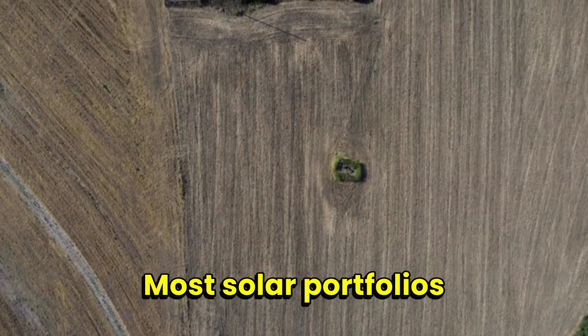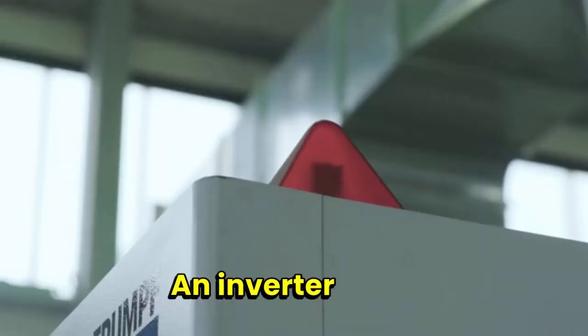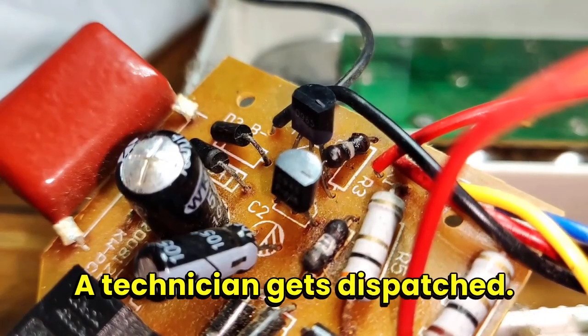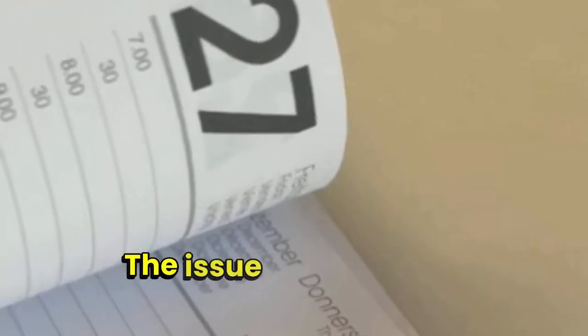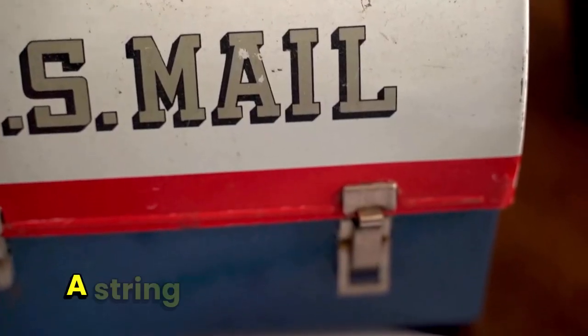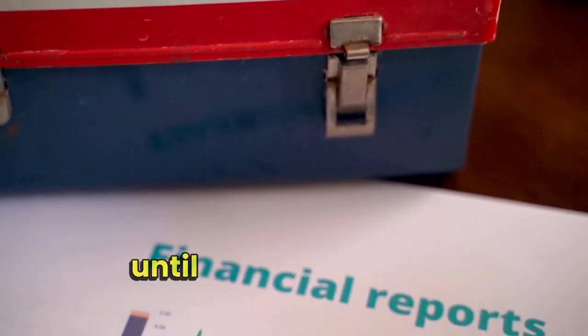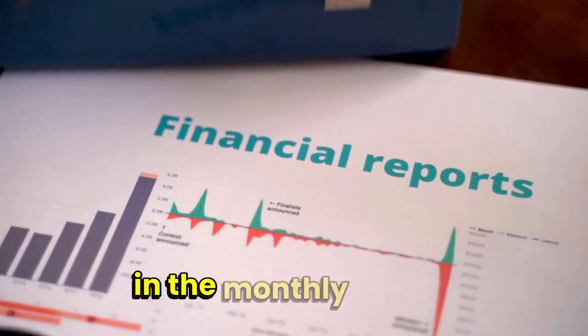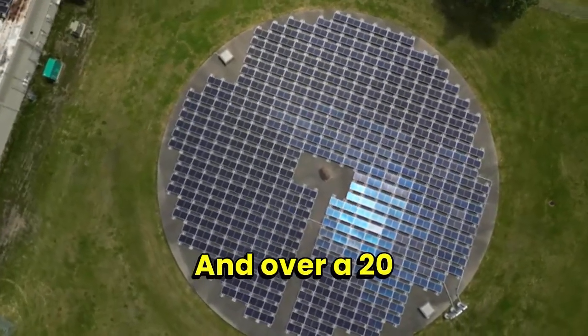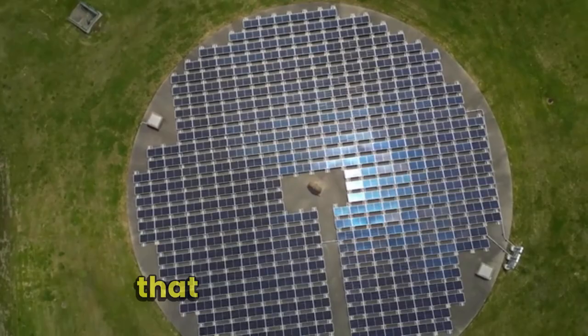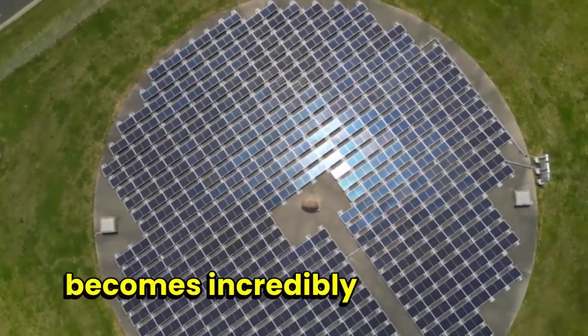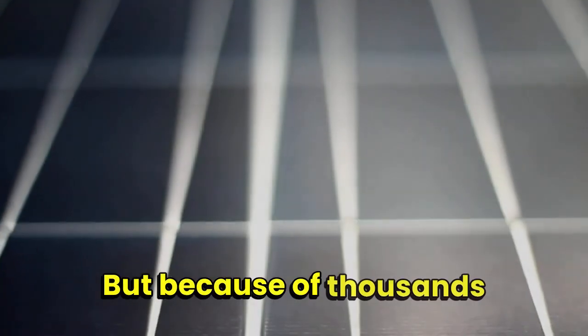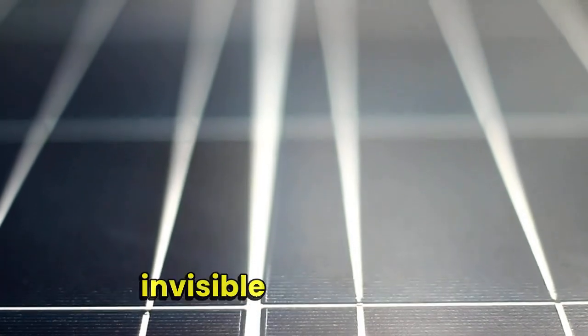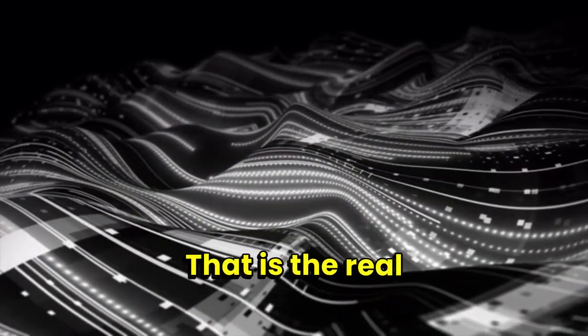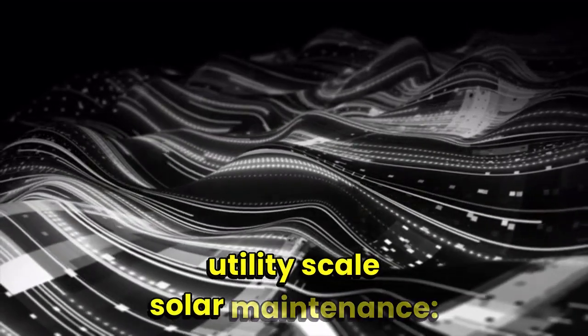Most solar portfolios still operate reactively. An inverter trips, a technician gets dispatched, a connector overheats. The issue is discovered weeks later. A string underperforms quietly until someone notices the revenue gap in the monthly report. And over a 20 to 30-year asset life, that operating model becomes incredibly expensive. Not because of one catastrophic failure, but because of thousands of small failures that stay invisible for too long. That is the real challenge with utility-scale solar maintenance.